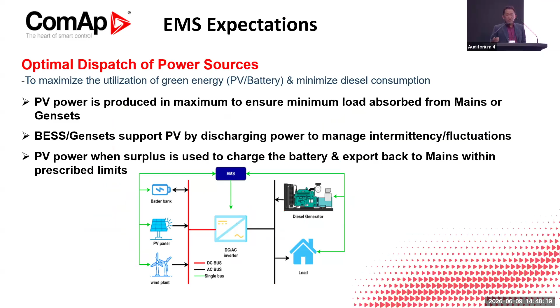Another important part is power management of sources. We need to curtail power when your PV harvests much higher than the load can consume. You have very low load but high PV harvest, so we need to do zero export control to ensure no reverse power to the utility, or worse, if it reverses power back to the generator, your generator ends up being a motor.